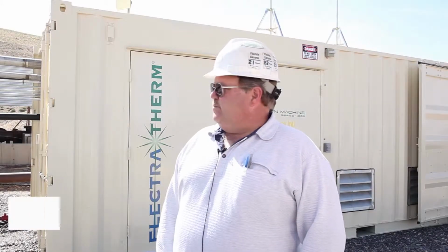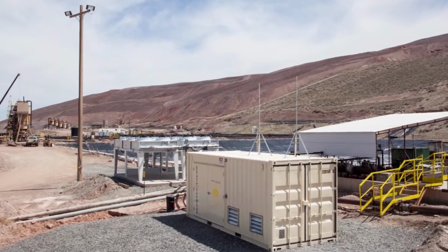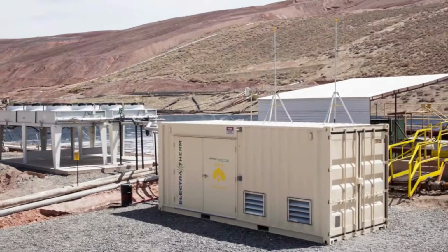The machine behind us here is actually the second ElectraTherm machine we've had on site. This is Phase 2, with modifications made from the original machine that was tested. It provides about 50 kW of power. It's worked very well. All our freshwater makeup water here is geothermal, coming out of the ground at roughly 230 some degrees, and we use that waste heat.